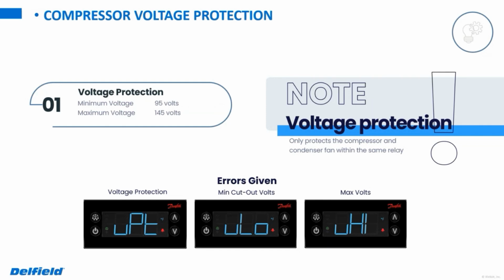So the classic example is new construction. There's an outlet that's been marked for 120. The electrician accidentally wires it for 220. Customer plugs the unit in. All of a sudden, we've got 220 going to a 120 volt cooler. So in that scenario, the control will cut power to the condenser relay, so we're not damaging those expensive, high-dollar components on there.